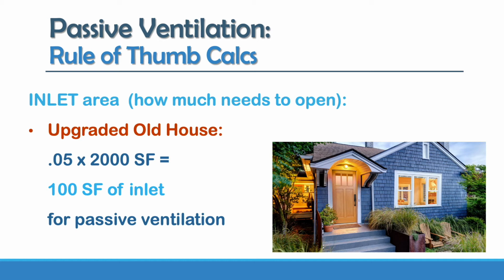As I mentioned, this can also be done by the room. So 5% of a 200 square foot room is 10 square feet of inlet. And for a more modest 100 square foot room, a 10 by 10 room, you would need 5 square feet of inlet.